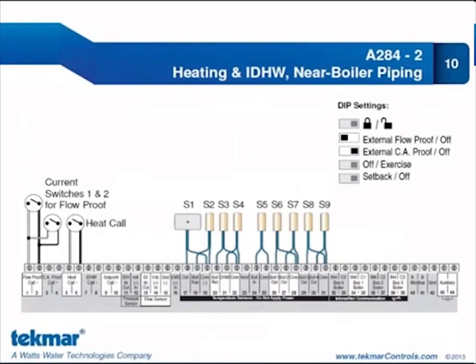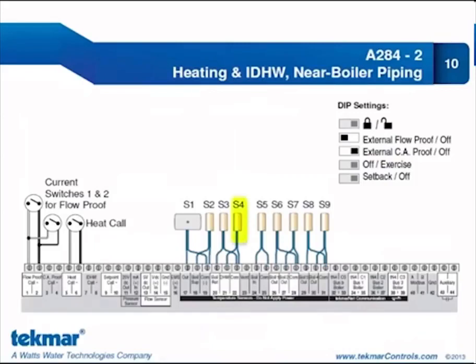For the flow proof call terminals, in this application we are using current switches to provide proof of flow. Those two current switches are connected in parallel to the flow proof call terminals, and since we are doing proof of flow, the DIP switch must be set to external flow proof. The heat call terminal is being switched, likely through a non-communicating thermostat such as one of our classic thermostats or the new 518 thermostat. We do not have an indirect domestic hot water call terminal connection because we are controlling the IDHW with a domestic hot water sensor. Sensors include outdoor, IDHW, boiler supply, boiler return, boiler inlet, and individual boiler outlet sensors.